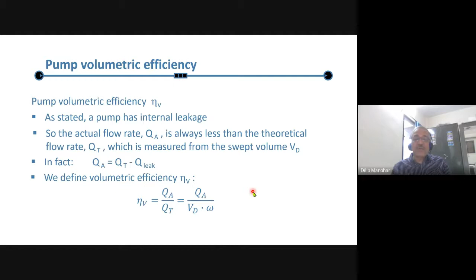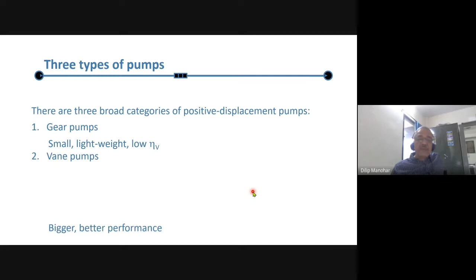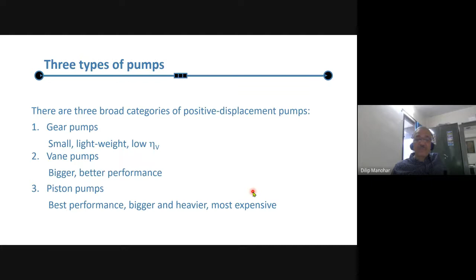There are three categories of positive displacement pumps. We will not go into much detail about the others, but only roughly see the most important characteristics. What are the categories? Gear pumps are lightweight, low efficiency pumps, meaning a low volumetric efficiency design. Vane pumps have a better design with respect to volumetric efficiency, and are bigger in size. Piston pumps have better performance, meaning high pressure, but are bigger, heavier, and most expensive.